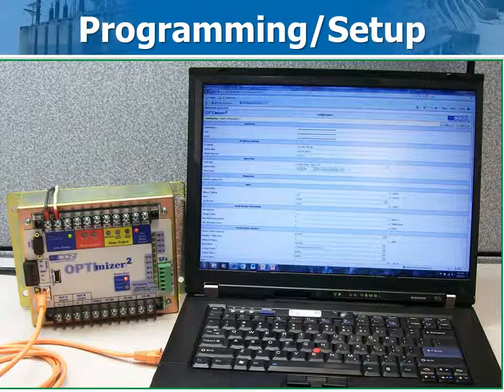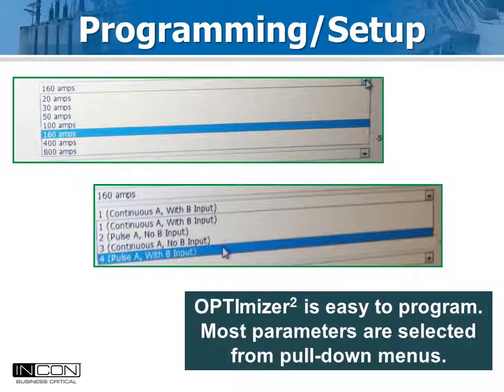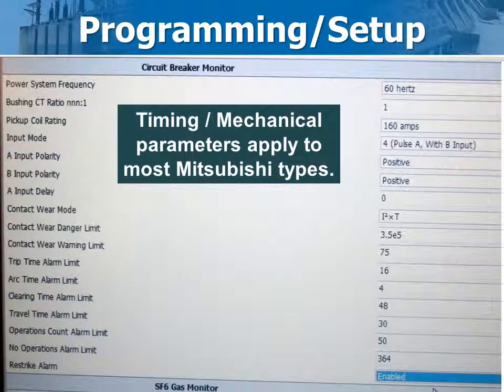Programming is most easily done at the office before you take it to the field. The Optimizer 2 ships from the factory with a default IP address. Use an Ethernet cable to log into the box using a web browser. Setup is easy. Most parameters are selected from pull-down menus. This part of the screen selects timing parameters that measured times are compared to for alarm purposes. These values shown are common to these Mitsubishi types.